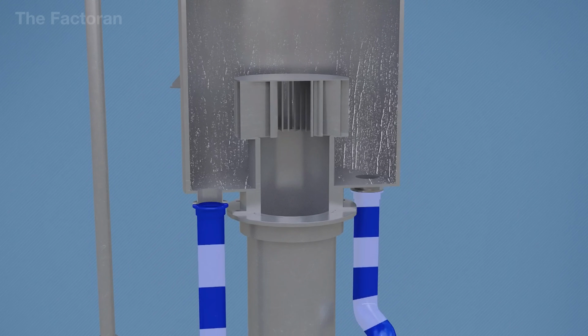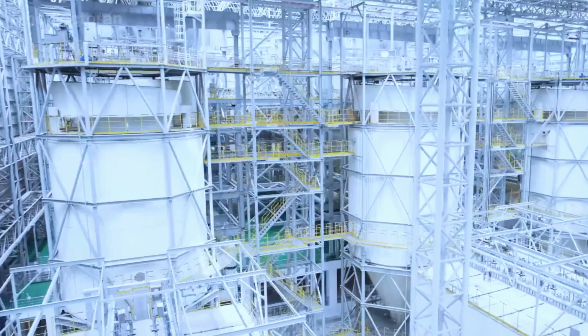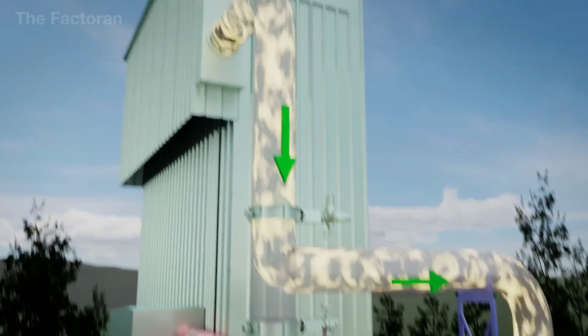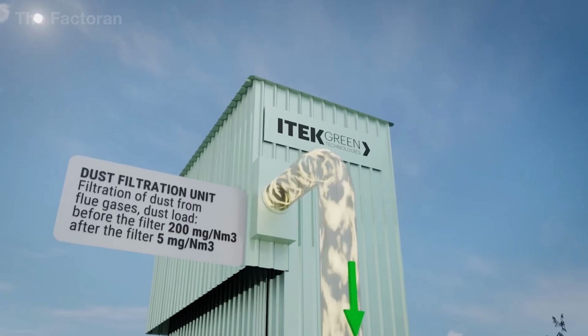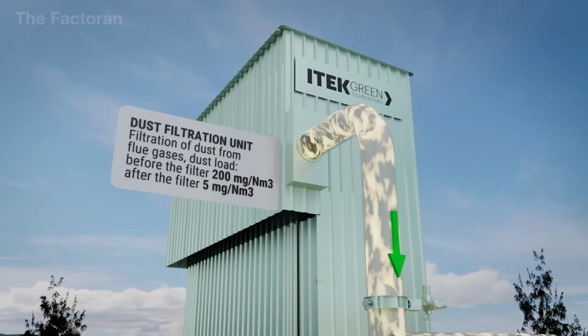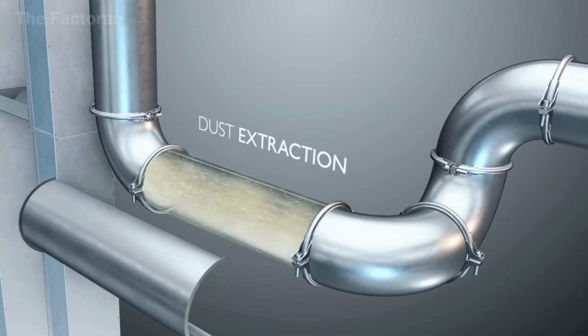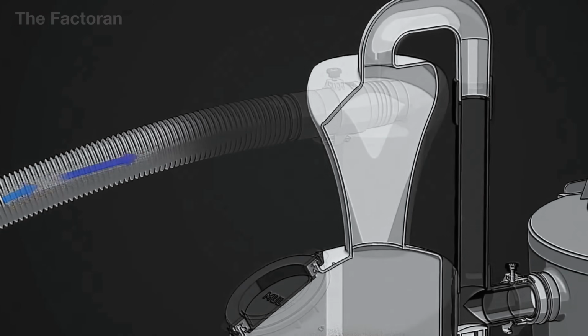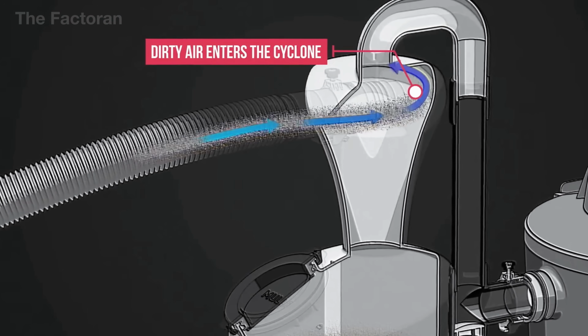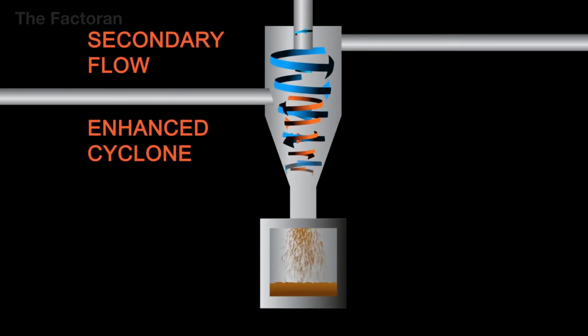After being cooled, the exhaust gas still contains a significant amount of coarse dust and suspended solid particles generated during combustion, grinding, or material heating processes. Before entering fine filtration units, the gas is routed through a primary dust separator, typically a cyclone separator or an inertial settling chamber.